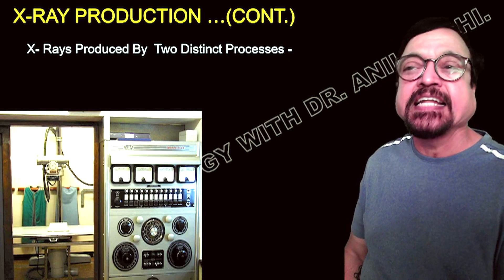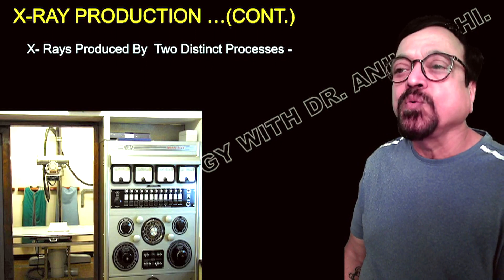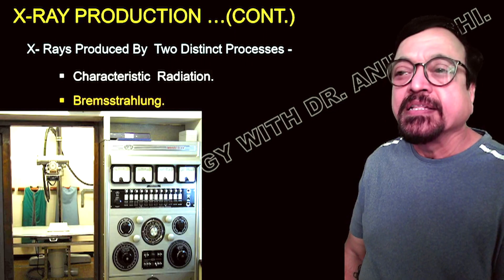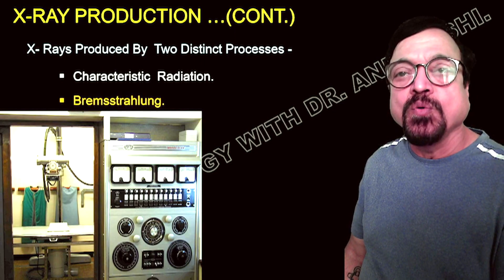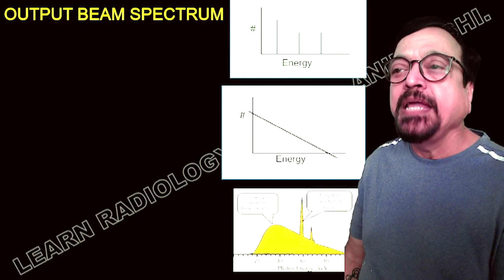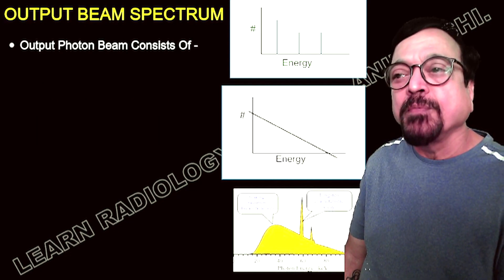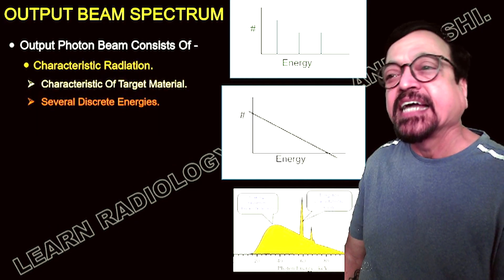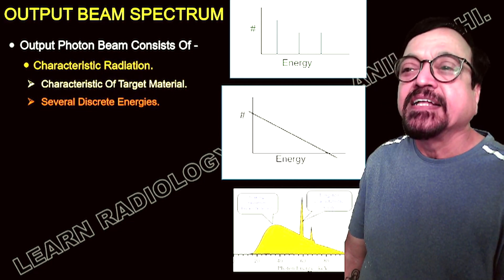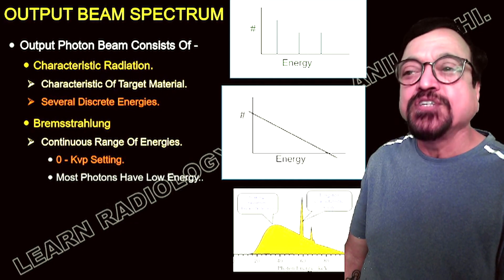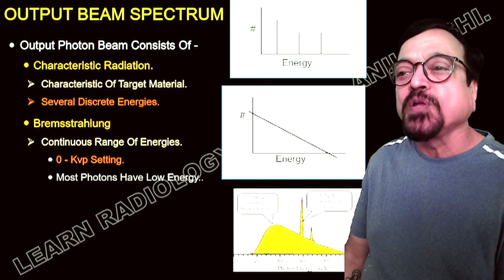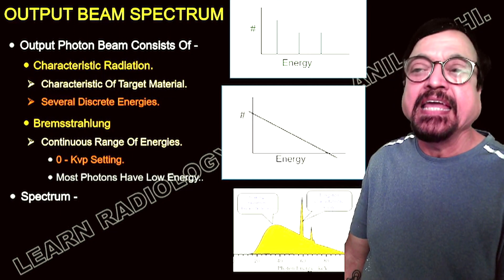X-rays are produced by two distinct processes. The first is characteristic radiation. The second is Bremsstrahlung — a German word meaning 'to decelerate' or 'to stop suddenly.' The output beam spectrum shows which part is characteristic radiation and which is useful. Bremsstrahlung is a continuous range of energies ranging from zero to the kVp setting, so most of those photons have low energy and make no contribution to the diagnostic imaging process.